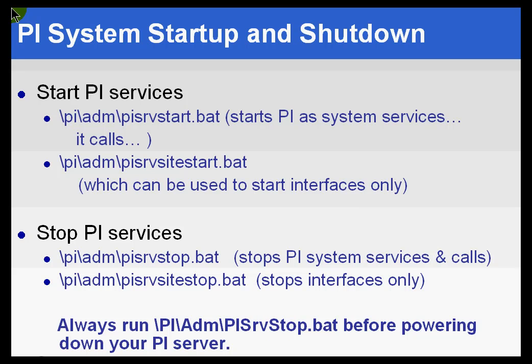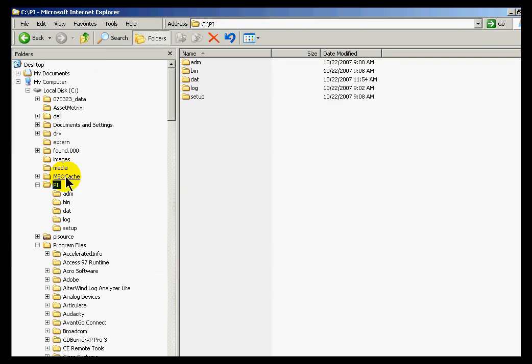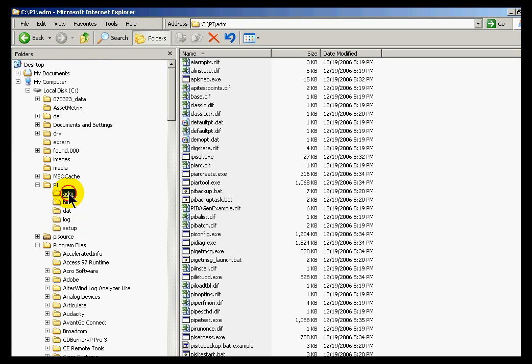Now, take a look in the PI directory and you'll notice one more batch file that you could use. This is in the PI slash ADM directory. It's called simply pistart. So here is the pisrvstart.bat, here's pisrvstop.bat, and then there's this pistart.bat. That's simply used for debugging purposes. We suggest that you don't run that unless you're trying to start up PI what we would call interactively instead of as a service.